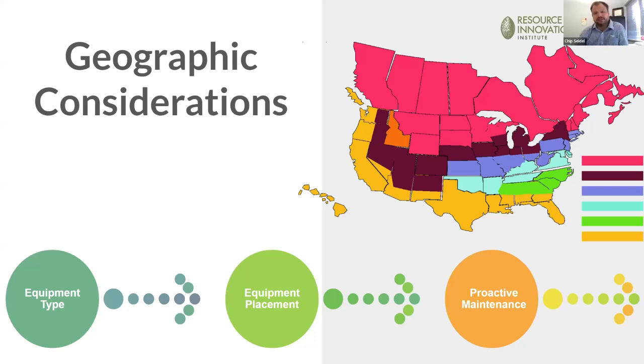There are other considerations for geographic location. A lot of this equipment will be outside, so you've got remote condensers and cooling towers for your chiller system. You're going to want to think about what airborne particles are in your region. If you've got a lot of milkweed or other stuff in the air at certain times of year, maybe your coils need to be cleaned more frequently. It's as simple as this: if it's a very harsh climate, maybe you won't want to locate your equipment on the roof. It might be better to have it in an equipment closet or mezzanine because of ease of service and other considerations.